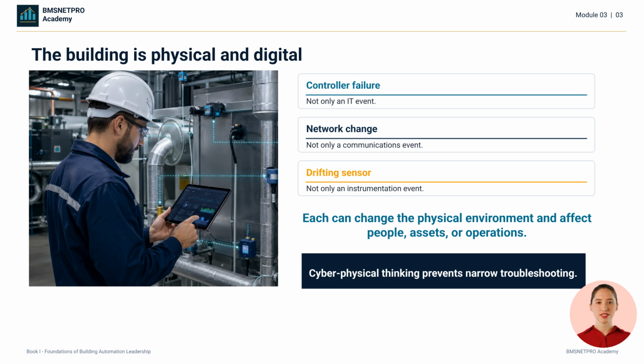The word cyber-physical helps us avoid a narrow view. A controller failure is not just an IT issue. A network change is not just a communications issue. A drifting sensor is not only an instrumentation issue. Each event can change a physical process and affect people, equipment, or operations. That is why the BAS manager must understand both sides of the building, the physical side and the digital side.